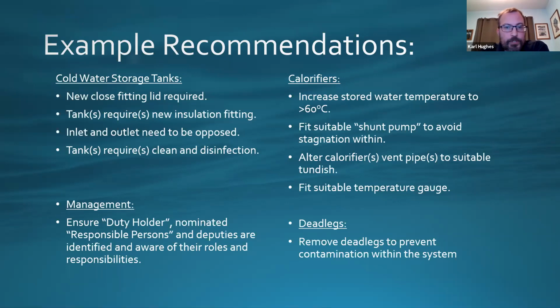Calorifiers, you need to make sure that temperature is above 60 degrees. If it's a larger cylinder, you'd need to make sure the shunt pump is installed. And what that does is it's designed so, for example, when the cylinder's not being used, say during the night, the hot water will bypass from the outlet, drop down through a circulation pump into the inlet, and what that's doing is destratifying the water within the cylinder. So you're giving the cylinder 60-degree water temperature throughout.